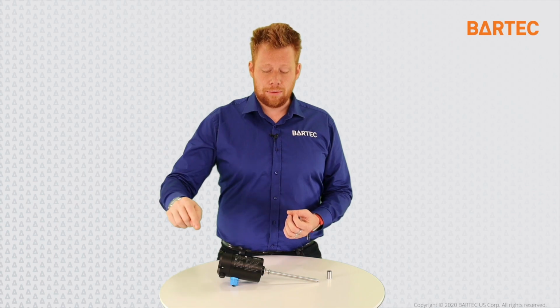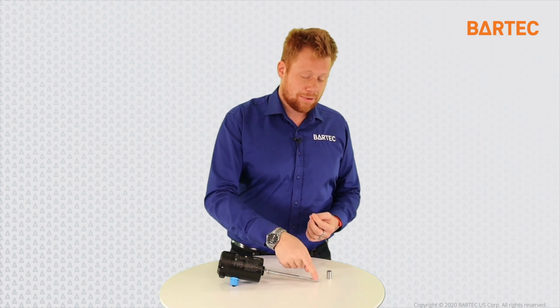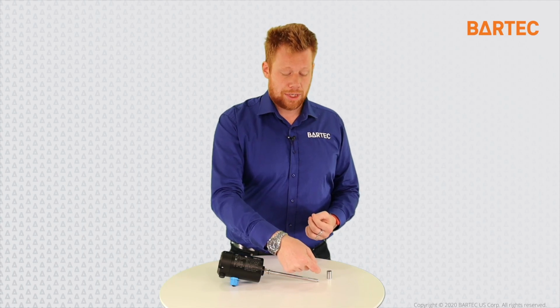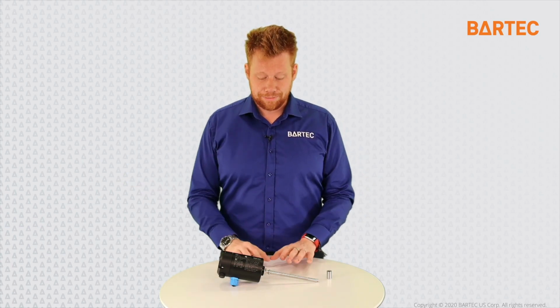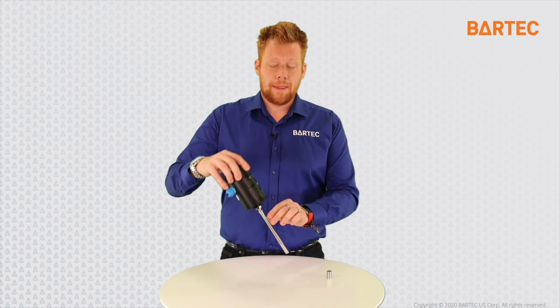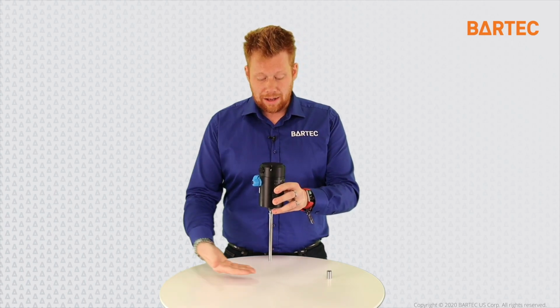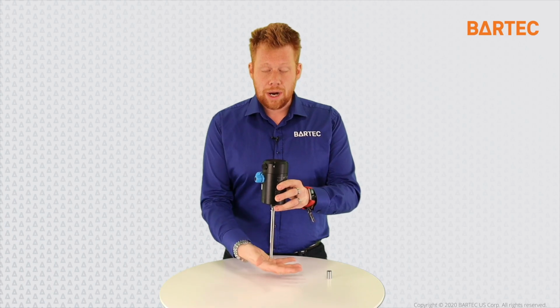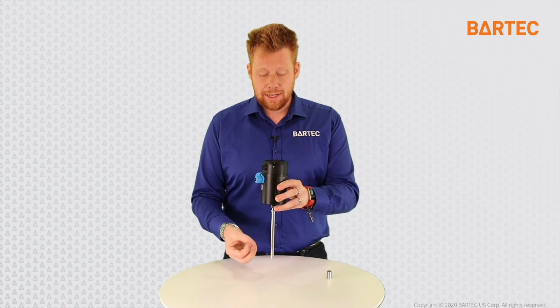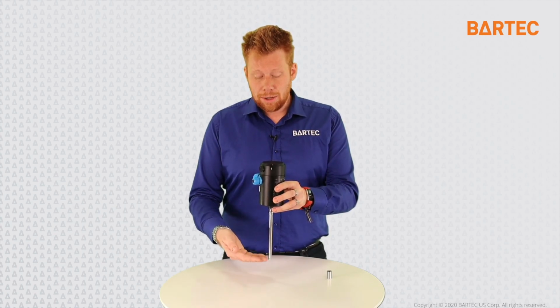As I mentioned, in the evaluation unit, we have a light source. The light is beamed from the evaluation unit through the fiber optic all the way to the probe. It goes to the tip and then enters the glass substrate. As it exits, it returns through the same path to the evaluation unit. Now, this probe is installed in the process, and we have the sample flowing around the probe and around the glass substrate. Depending on the amount of moisture inside the sample, the substrate will get loaded more or less with moisture, based on basically osmosis.